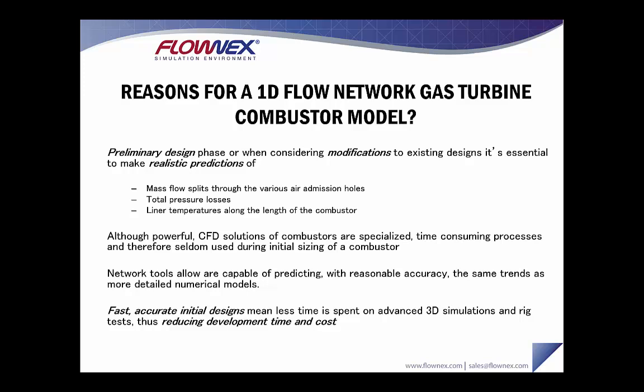During the preliminary design phase, or when considering modifications to an existing design, it's essential to make realistic predictions of mass flow splits through various air admission holes, total pressure losses, and liner temperatures along the length of the combustor. Although CFD solutions of combustors are quite powerful, they are specialized time-consuming processes and are therefore seldom used during the initial sizing of a combustor. Network tools allow you to predict with reasonable accuracy the same trends as a more detailed numerical model, with the added benefit of being really fast, allowing accurate initial designs and ultimately reducing development time and cost.